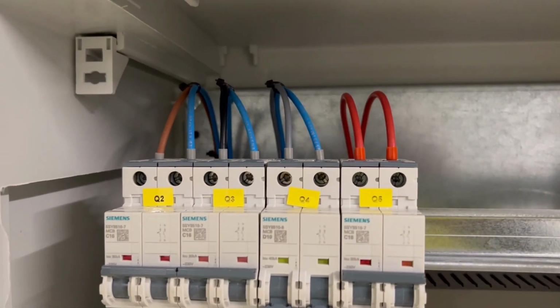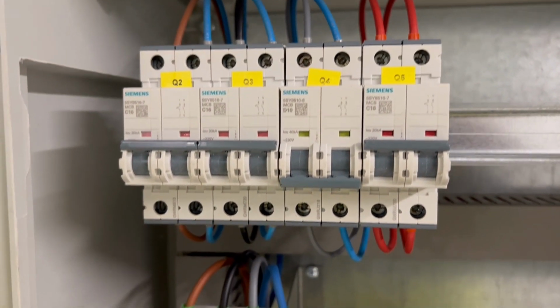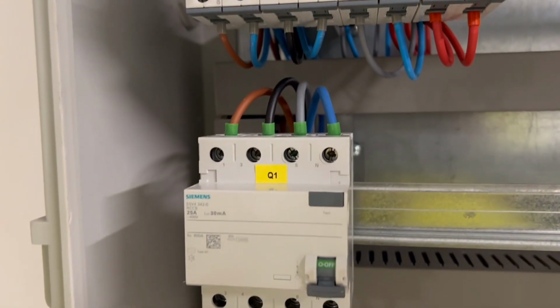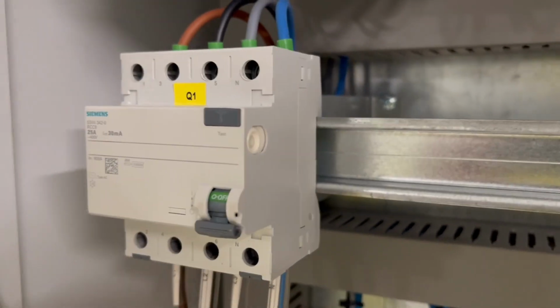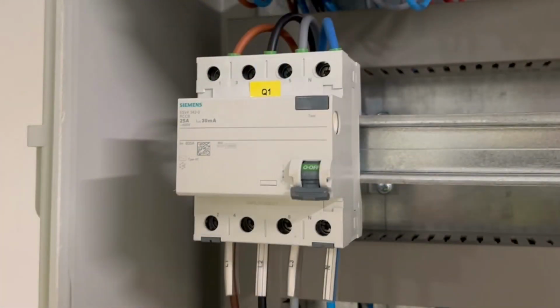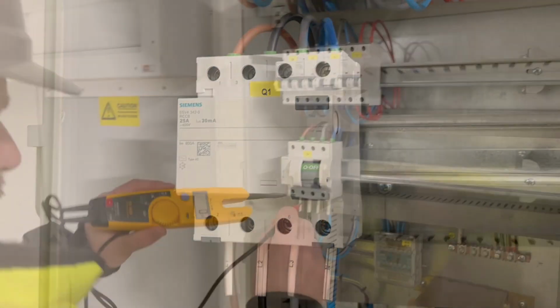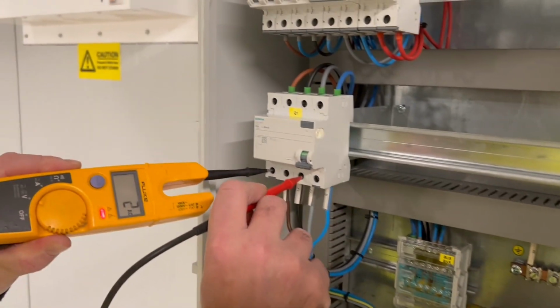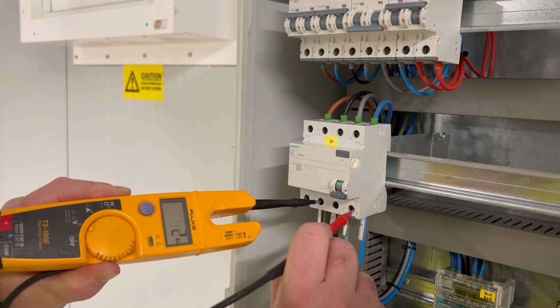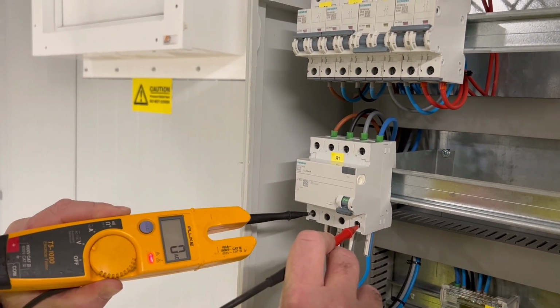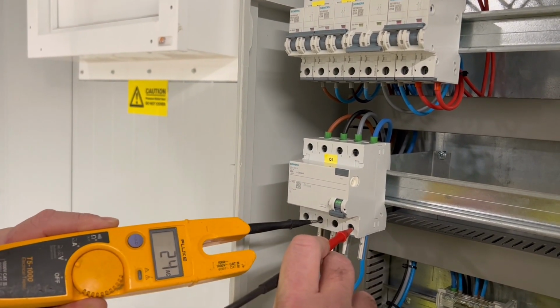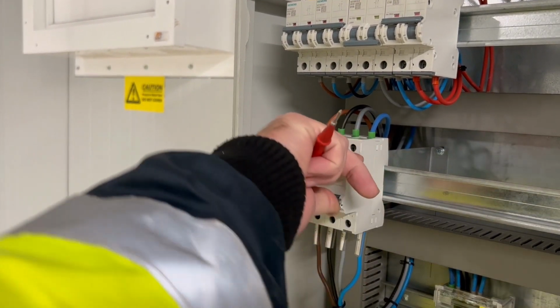Inside the socket box we have outgoing circuits, double pole circuit breakers, and this is the incoming RCD device. This one under test is 25 amp 30 milliamp personal protection. First, because we've been doing HV switching across the network today, we've got to check we've got incoming voltage within the tolerance. So we check the incoming voltage quickly.